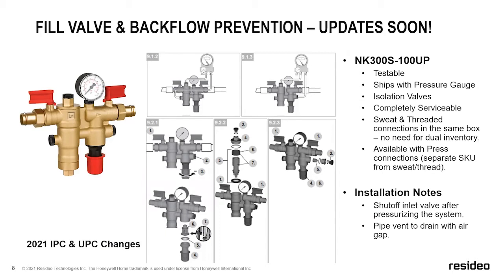We do also have test ports. If you look at the top couple of grayscale images that I have there, it kind of shows how you test the 2 different check assemblies inside of here. So I do want to highlight that this is a testable dual check backflow preventer, as well as it's got a combination fill valve. So one thing I do want to touch on is we've had some changes within this.